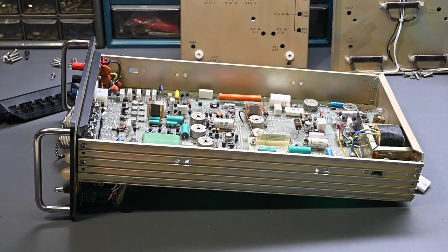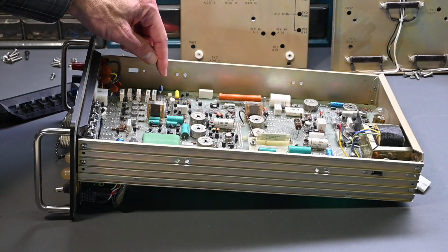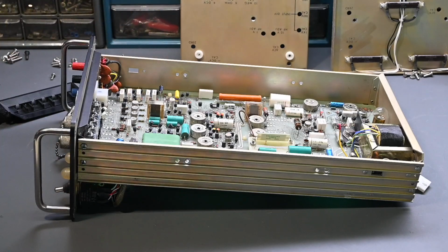Now, as you saw in part 1, there's an electrolytic capacitor right here that had excessive leakage current when I removed it and did that leakage test with my Sencore capacitor tester. And I'm sure that the other electrolytic capacitors are probably in a similar state of condition, just given that here in 2025 this instrument is nearly 50 years old. So even if replacing all the electrolytic capacitors doesn't solve the problem in the ring counter circuit, it'll still be a good idea just for the reliability of the instrument.